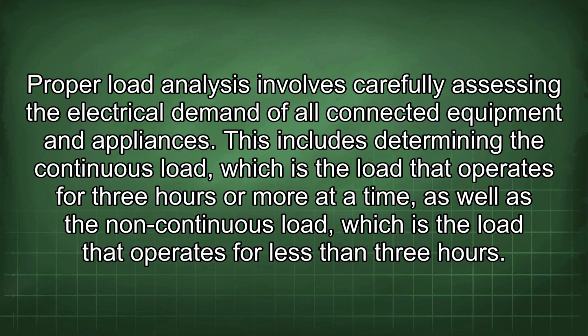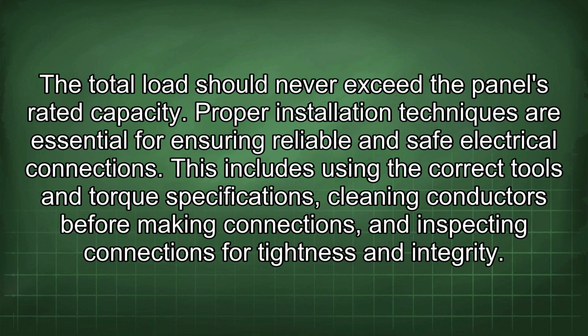Proper load analysis involves carefully assessing the electrical demand of all connected equipment and appliances. This includes determining the continuous load, which is the load that operates for 3 hours or more at a time, as well as the non-continuous load, which is the load that operates for less than 3 hours. The total load should never exceed the panel's rated capacity.